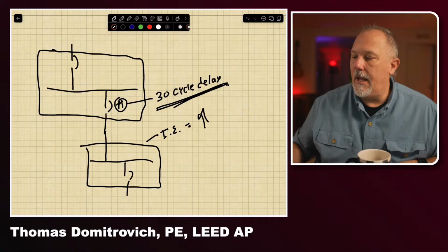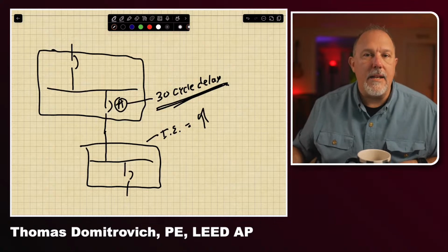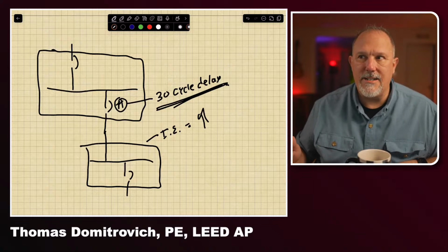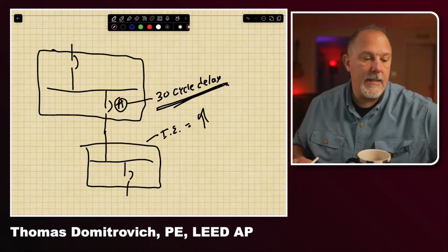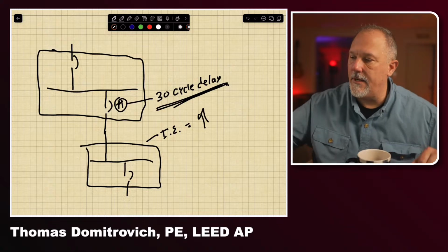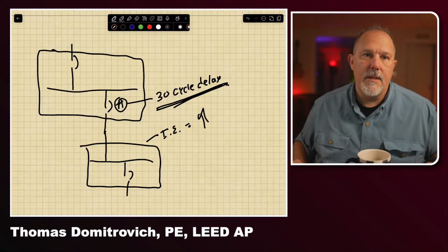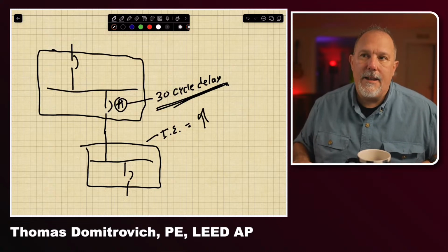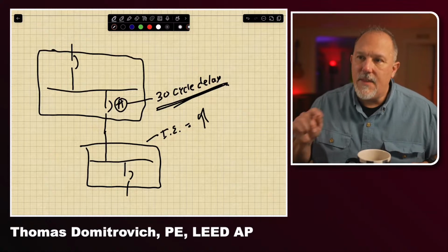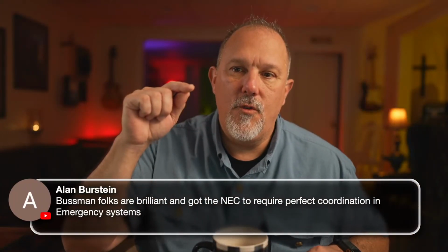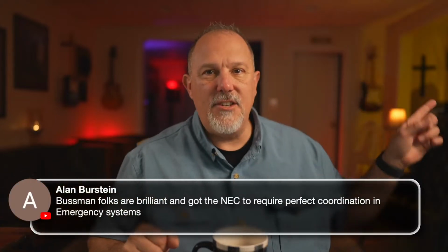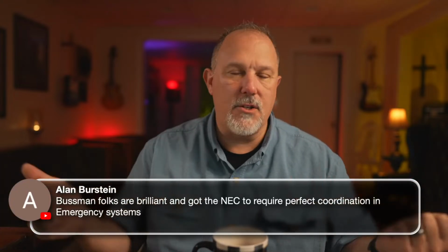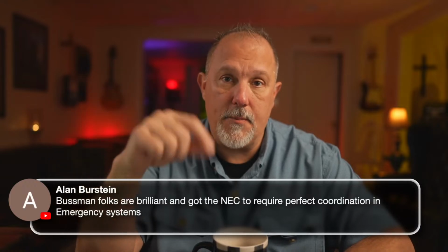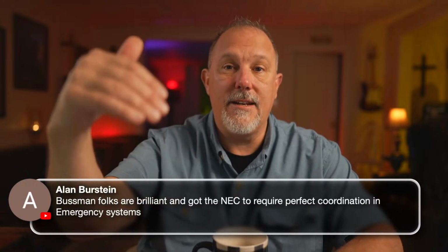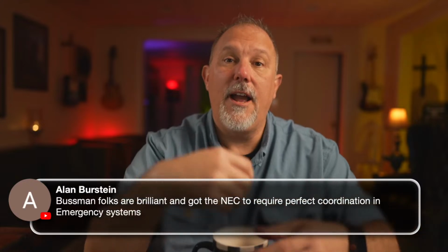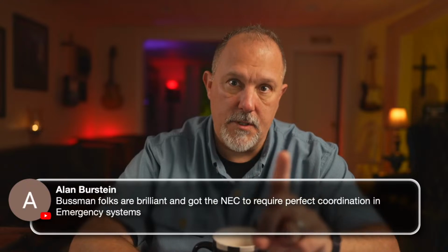And I couldn't understand how, from an IBEW perspective, our electrical workers, the IBEW was all over it. They supported it. And their reasoning was really enlightening for me. Tom, I had multiple people tell me this. They said, if there's a lack of selective coordination at, say, a large industrial application or commercial building, and you called me because the main tripped, they have to find the problem before energizing or turning anything back on again. If your main trips, there's a problem somewhere in this facility, and OSHA tells you that you can't just turn things back on. It makes it very difficult for them to identify where the problem is. But if it's selectively coordinated, they know exactly where the problem is. They can clear the fault, check the breaker, and then re-energize. It makes their life simpler and safer.